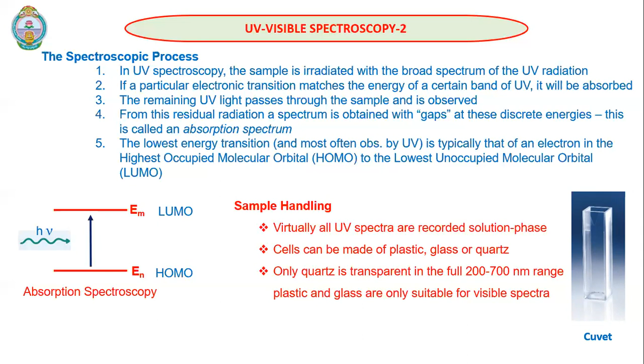Quartz is transparent throughout this full UV visible range, that is from 200 to 700. Generally, we can go from 200 nanometers to 900 nanometers. So for a UV visible instrument, we use quartz cells, which are generally called cuvettes. So cuvettes look like this. We prepare a dilute solution of the organic compound, place it in the cuvette, then place it in the instrument and we get the data.